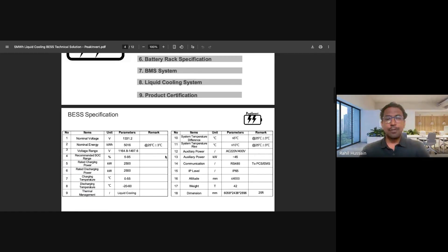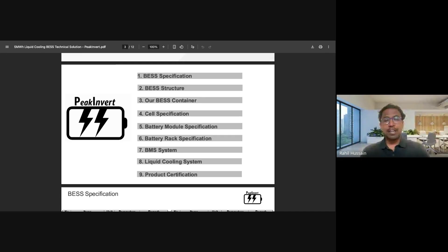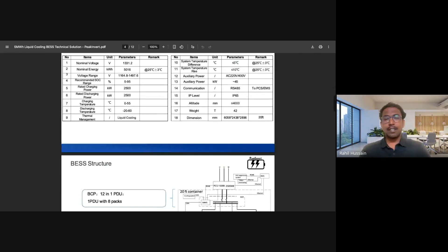We're going to see this 5 megawatt hour system in a 20 feet container. Let's see what it contains: cells, then cells combined into modules, then modules combined into racks, then the BMS system, and as discussed earlier, a liquid cooling system inside to control thermal runaway and prevent the BESS from catching fire.